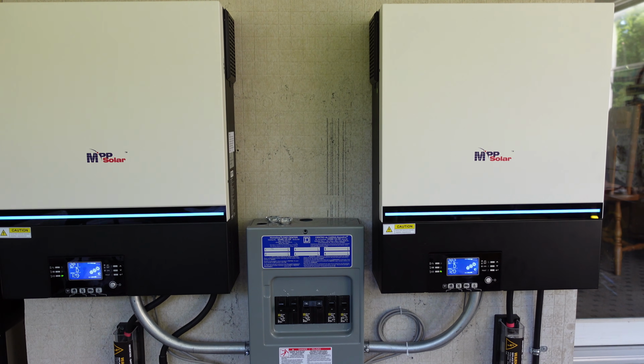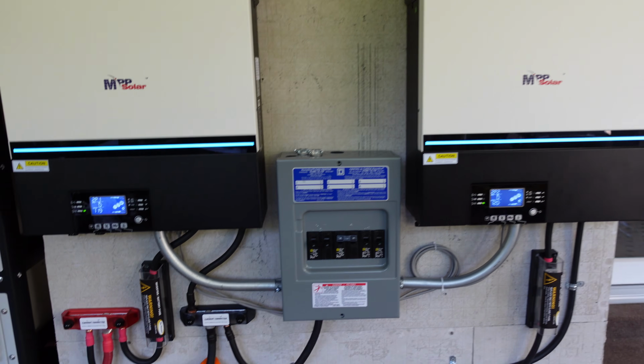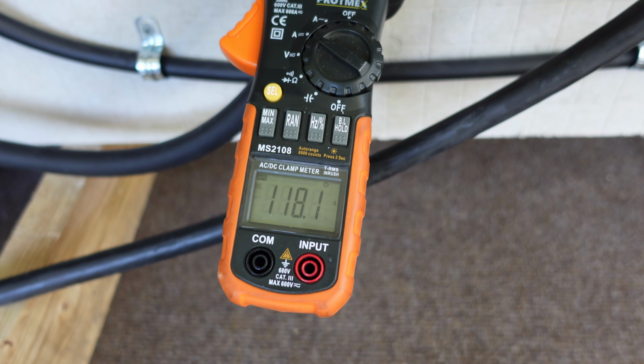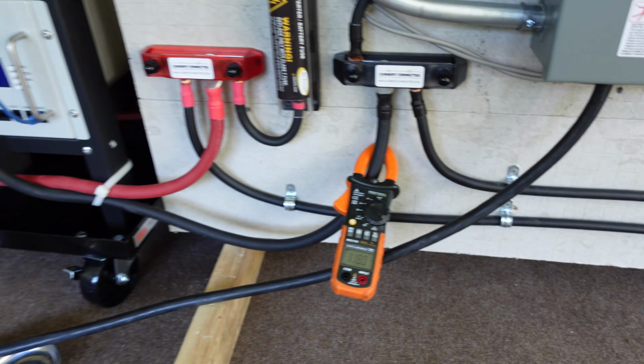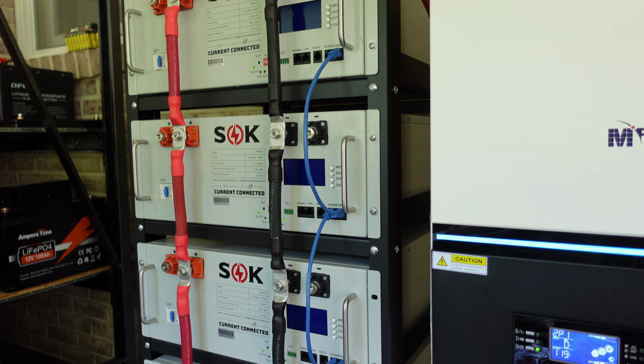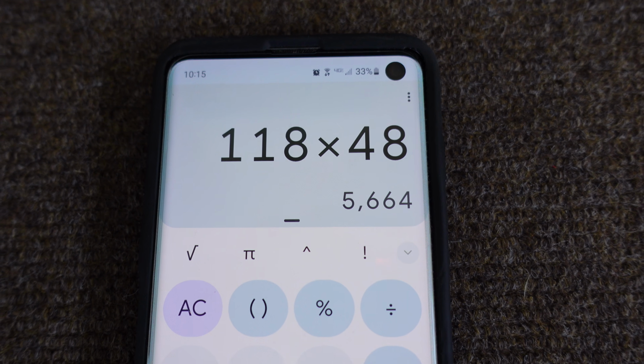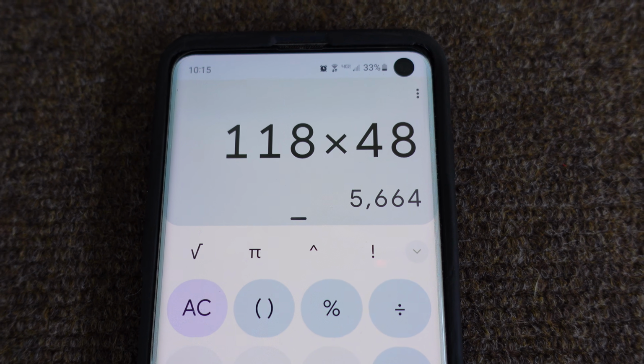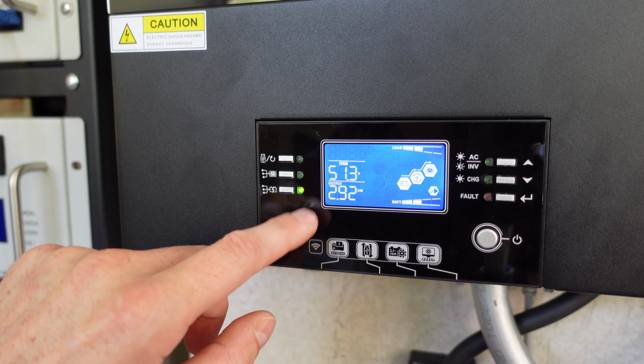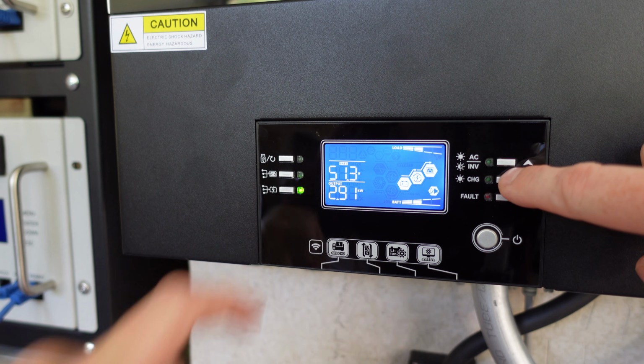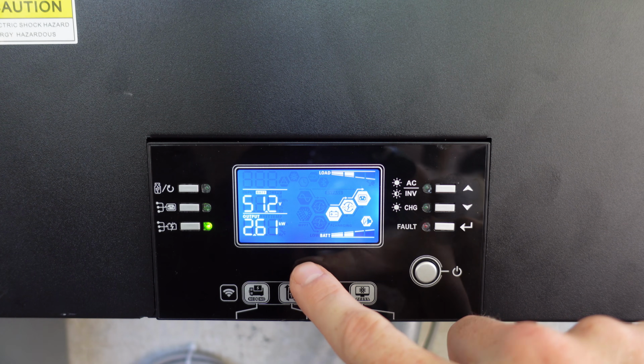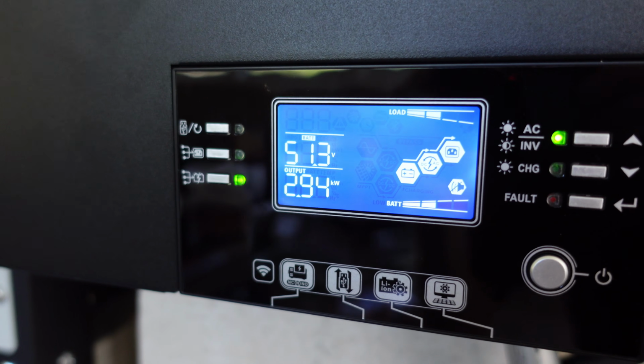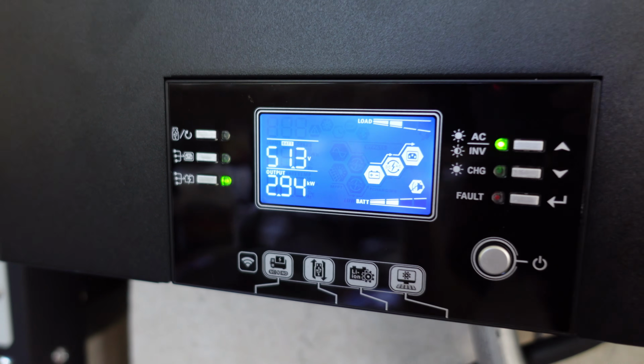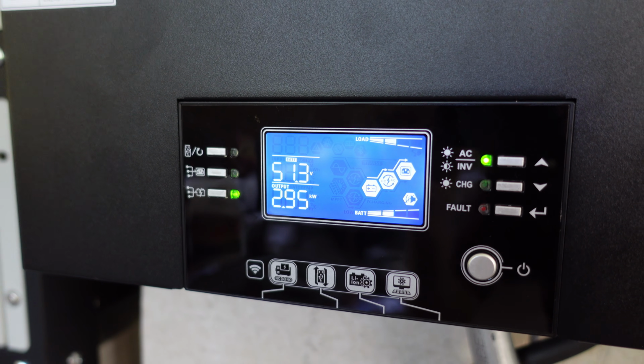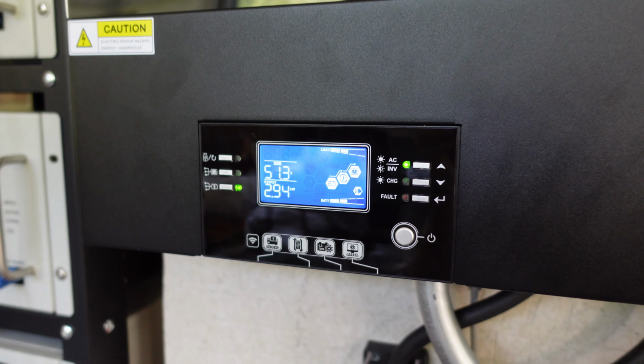All right, these inverter fans have gotten quite loud here. And we're pulling about 118 amps from our SOK battery rack here. And that is 5,664 watts. So I see on this inverter it's showing the load at 2.91 kilowatts. This one's showing 2.61 kilowatts. 2.94, not quite sure why that is. Maybe it's pulling some from the neutral lead, causing a slight imbalance.